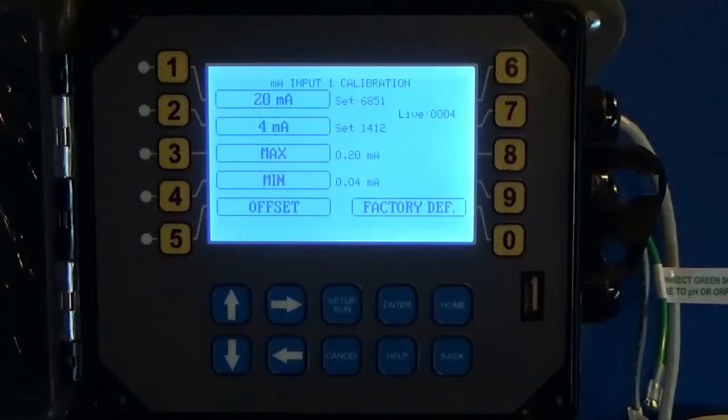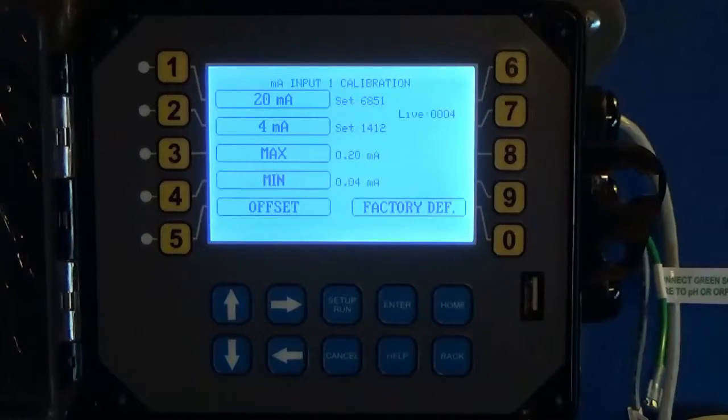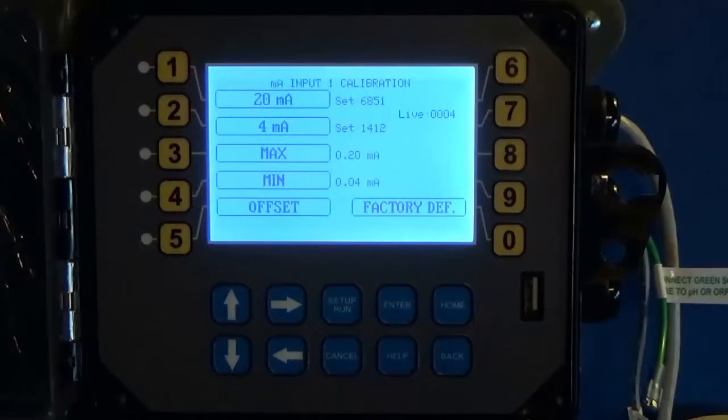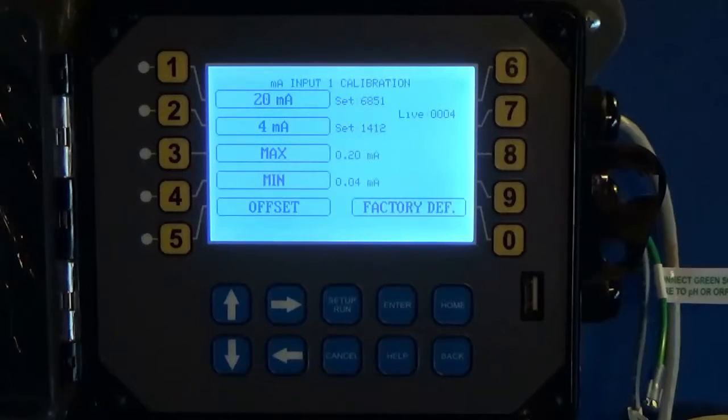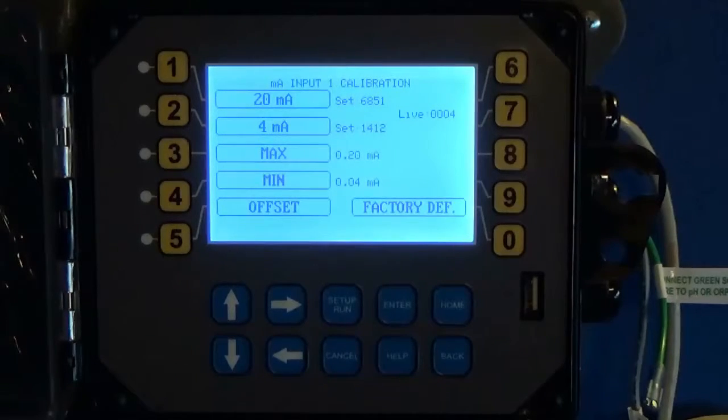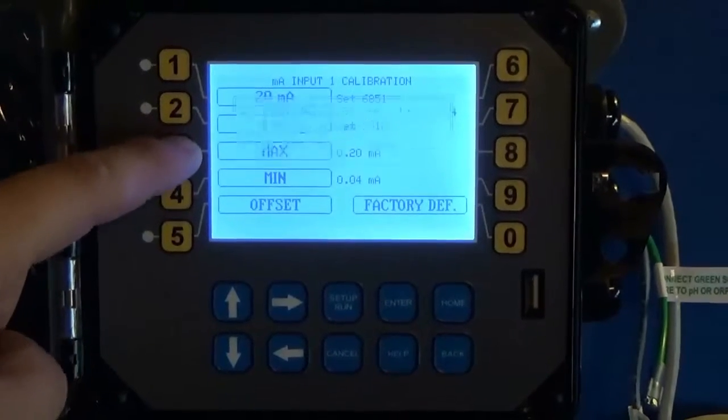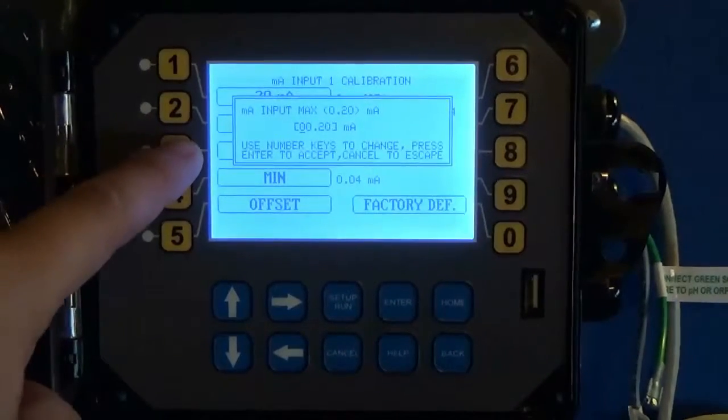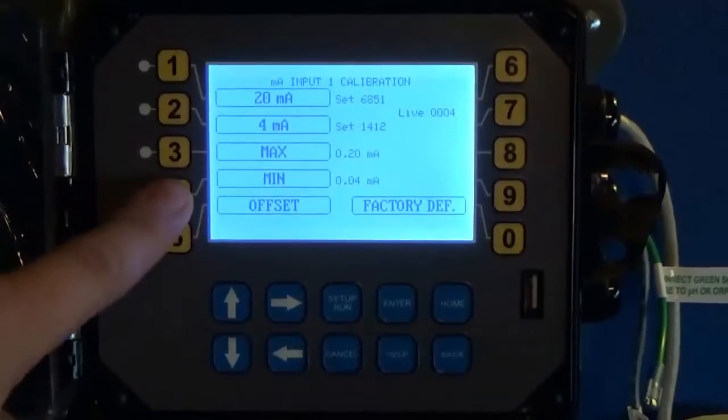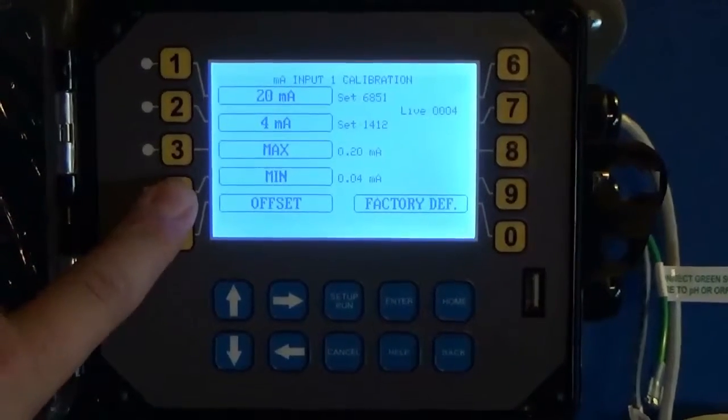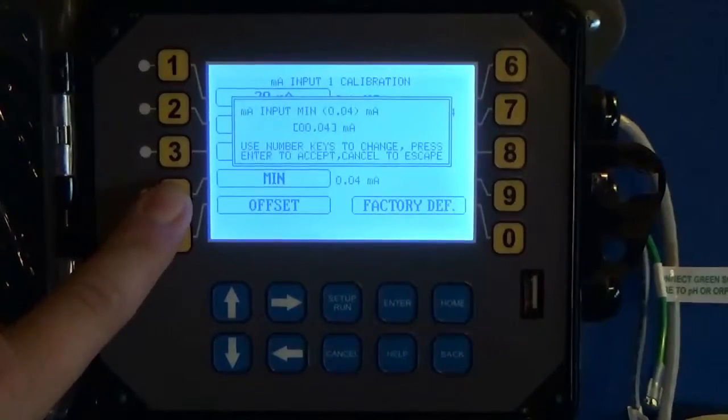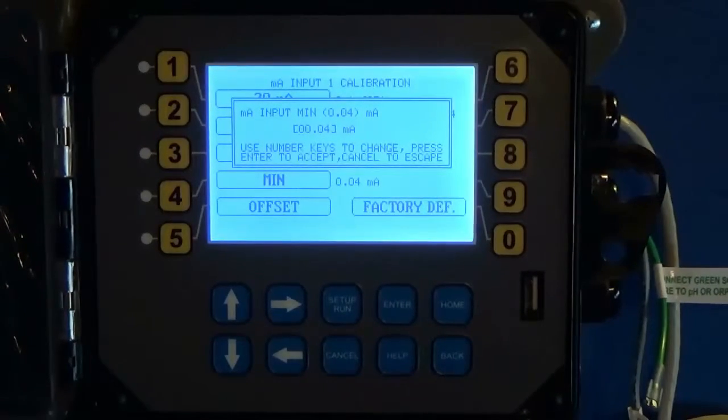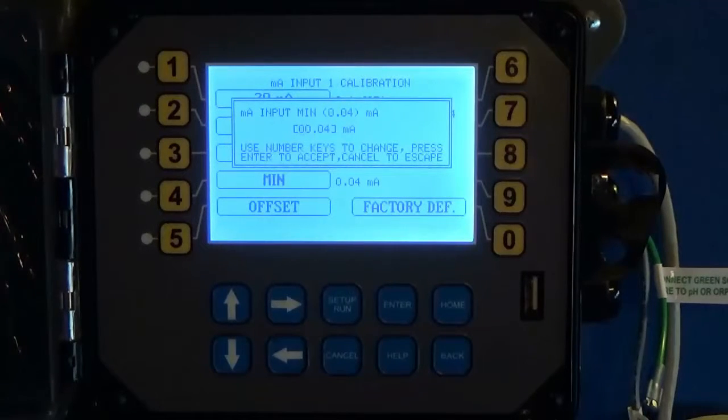Here's the screen where you're going to set your min and your max or your total range. If your sensor, say it's a pressure transducer, is a zero to 100 psi pressure transducer for instance, your max here would be 100 and your min here would be zero. Again, this all depends on what your product range is.